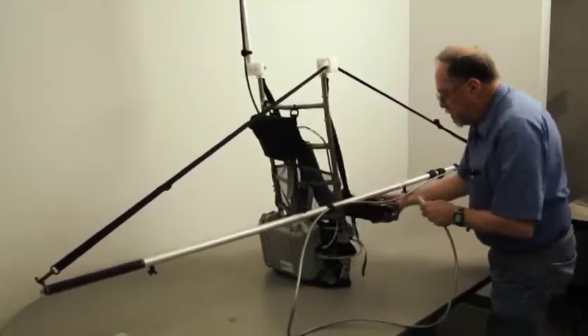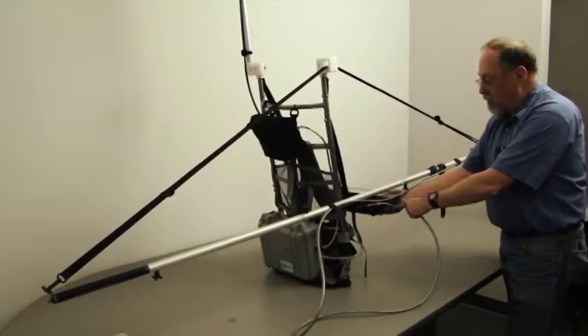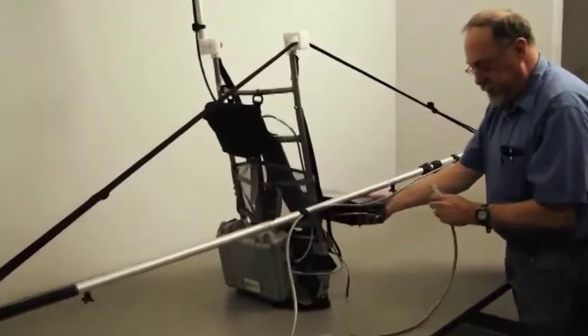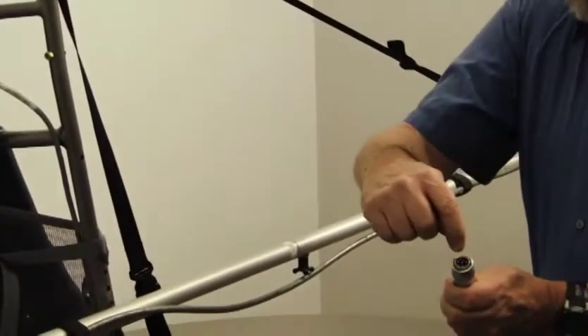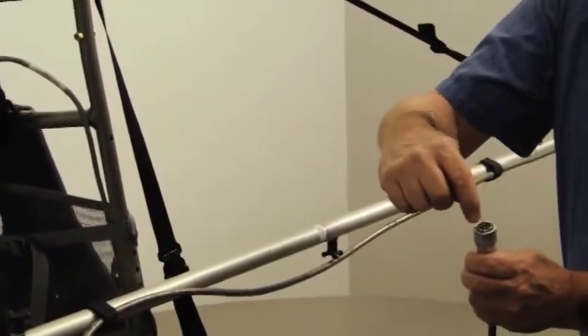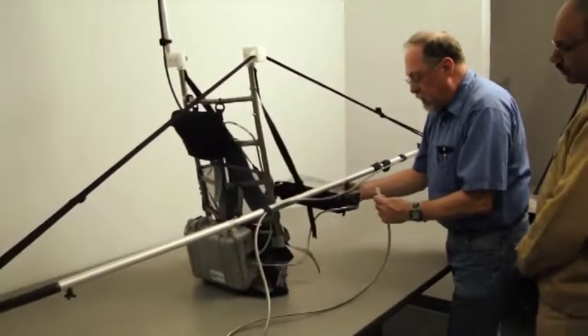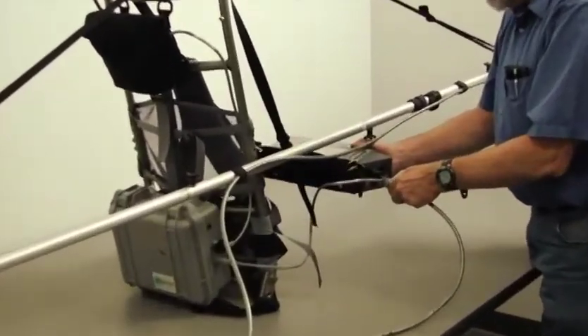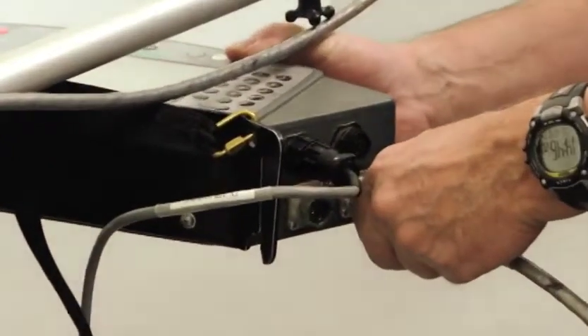A single sensor connects to the front port of the magnetometer. It's an aluminum colored metal connector. The sensor cable has keys around the outside of its connector. There's one wide key and four narrow keys. The wide key faces the front of the instrument. And you just gently put the cable next to the connector until it clicks in place. Don't use much force.